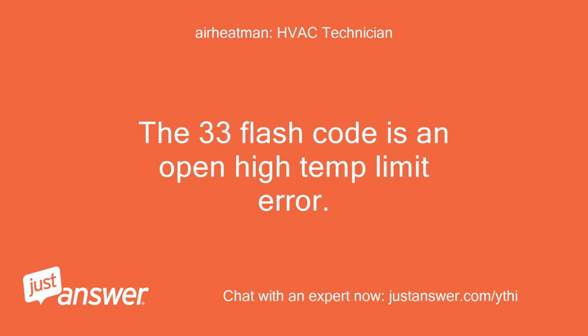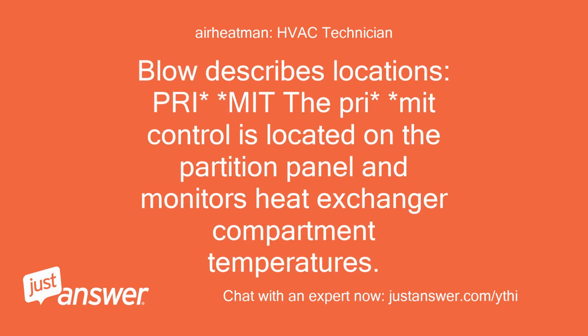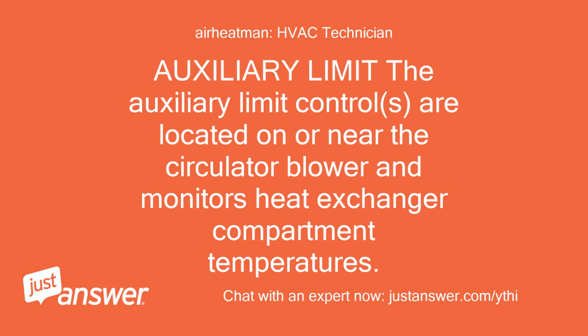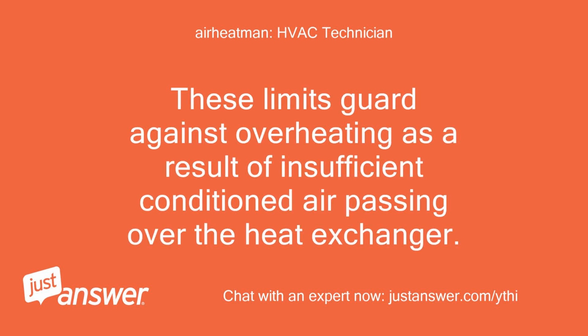The 33 flash code is an open high temp limit error. There may be several limits on the furnace. Below describes locations. Primary limit: The primary control is located on the partition panel and monitors heat exchanger compartment temperatures. It is a normally closed, electrically, automatic reset, temperature activated sensor. The limit guards against overheating as a result of insufficient conditioned air passing over the heat exchanger. Auxiliary limit: The auxiliary limit controls are located on or near the circulator blower and monitor heat exchanger compartment temperatures. They are normally closed, electrically, manual reset, temperature activated sensors. These limits guard against overheating as a result of insufficient conditioned air passing over the heat exchanger.